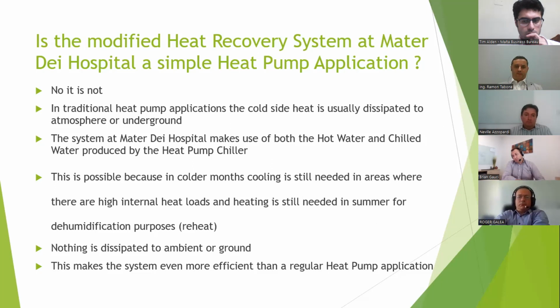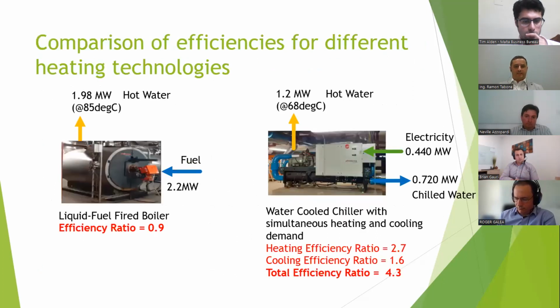Most of the plant rooms, and we have IT hub rooms, have an internal heat load that's still present in winter. So we still have a good amount of cooling demand in winter as well. So we have a situation where we have a minimal cooling demand in winter, but a high demand for heating. And in summer, we have a high demand for cooling, but still a high demand for heating because of the dehumidification purposes. As I said, no heat is dissipated to ground. This makes the system even more efficient than a regular heat pump. So basically, I have a comparison of both technologies here.